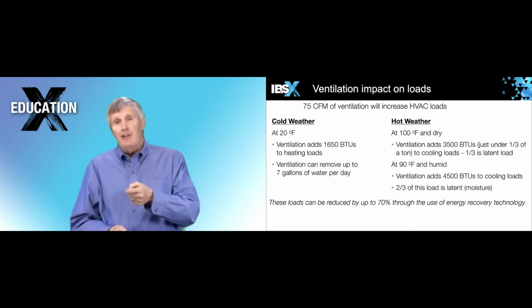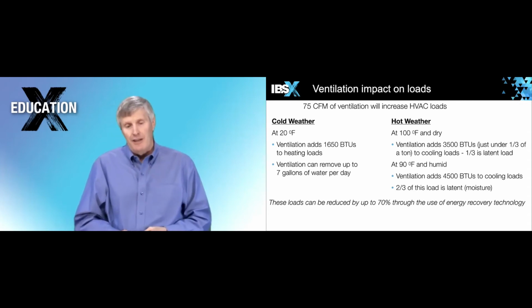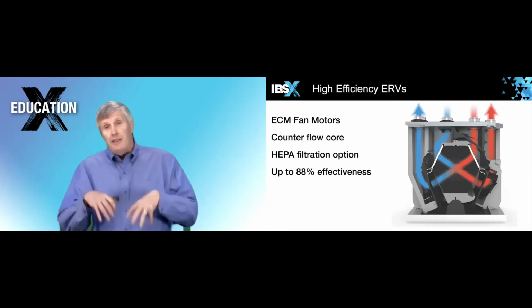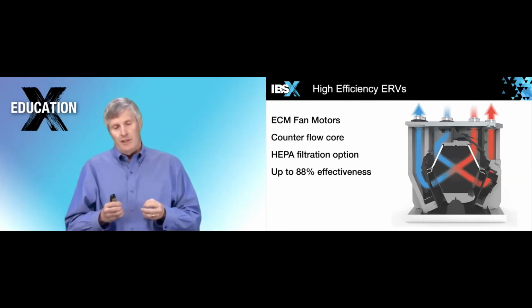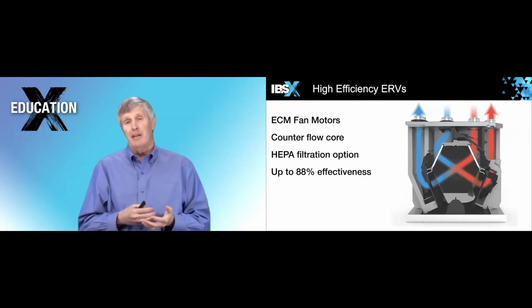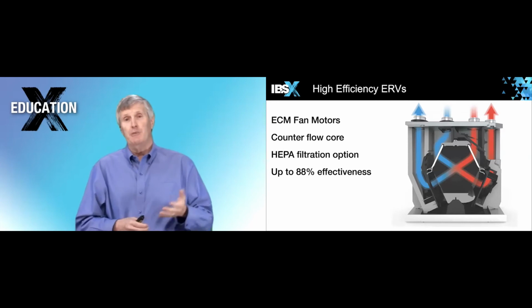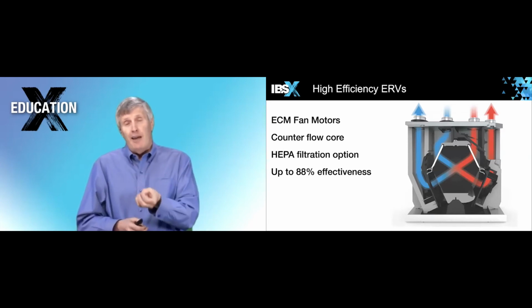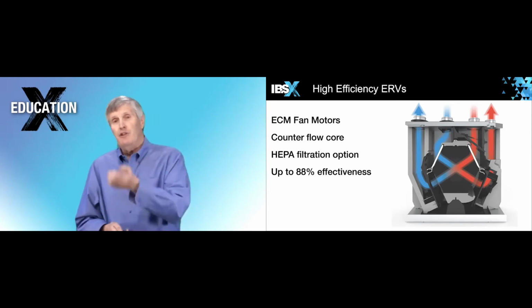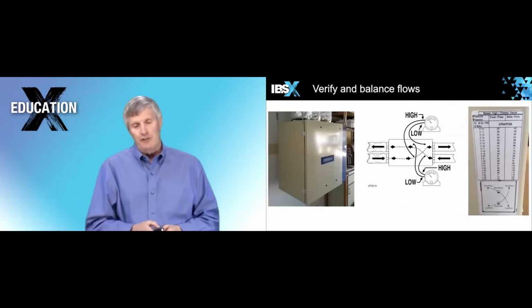So imagine using ERVs and what the impact would be on the loads. And it's really not that great a load. And so then there are high efficiency ERVs that have ECM motors that have efficiencies up to 70 or 80%, even this one's showing 88%. Some of them have HEPA filtration built into them. So those fine particulates from outside are first meeting a high efficiency filter so that you're not getting those pollutants from outdoors. So some really nice technologies out there these days.